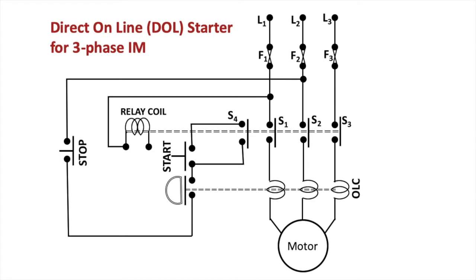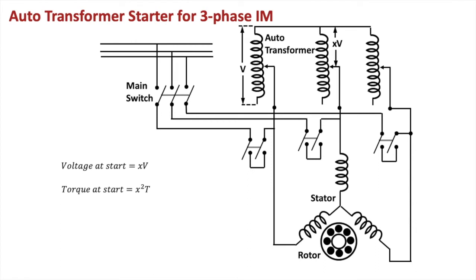Because there is no reduction of the voltage and no protection of the motor other than the overload protection and no-volt protection, the DOL starter is not used for the higher ratings of the motor. For the higher ratings, we can go for the auto transformer starter, where we can reduce the starting voltage, and if you reduce the starting voltage, naturally the inrush current will be reduced and the motor will be safe, plus there will be no drop in the supply system.